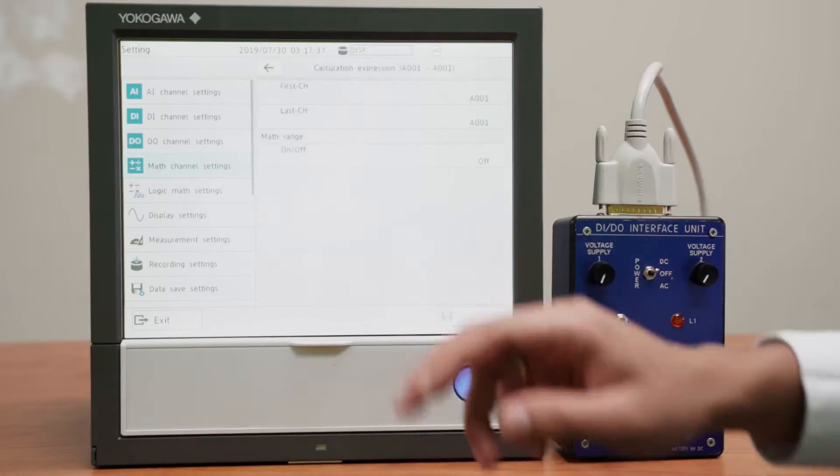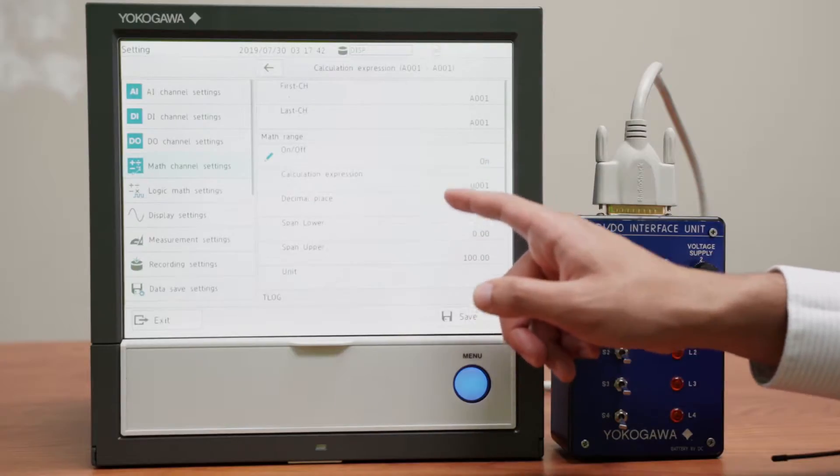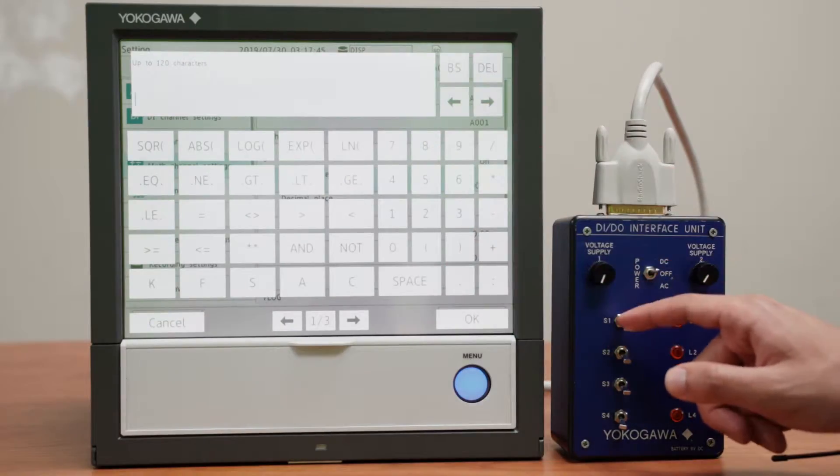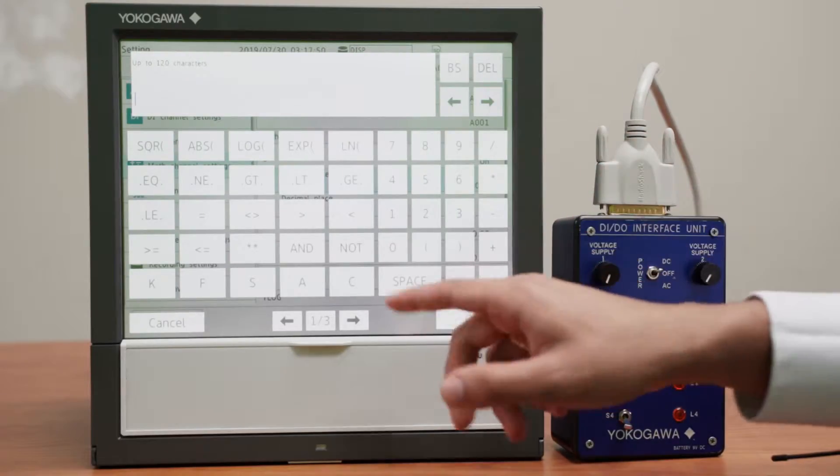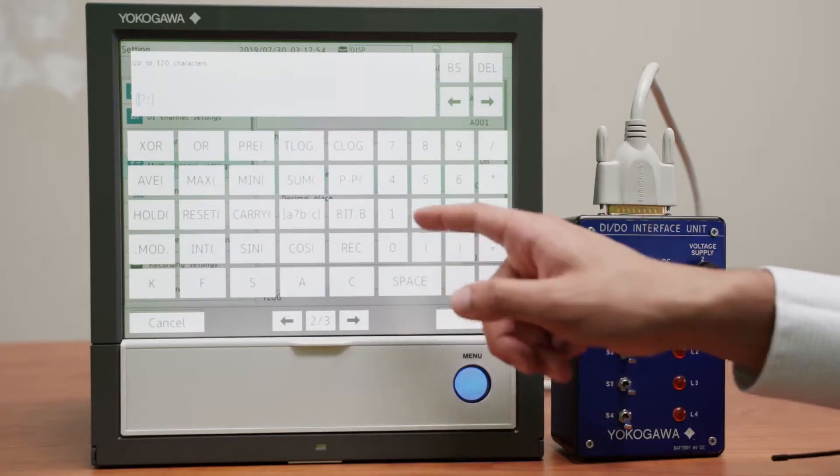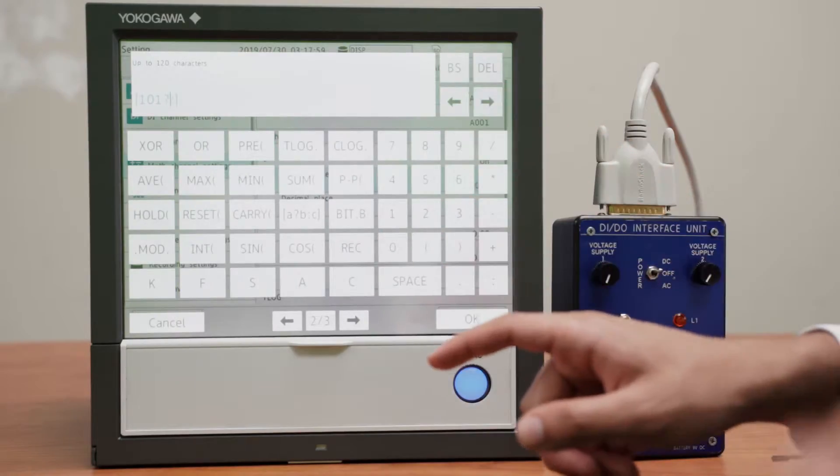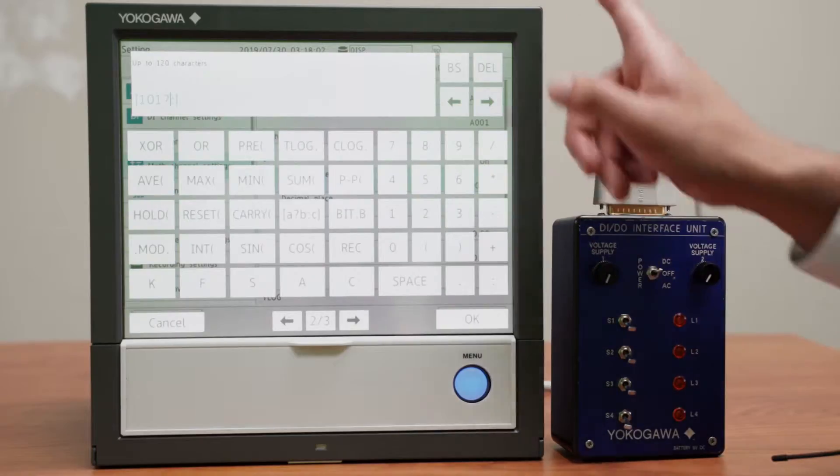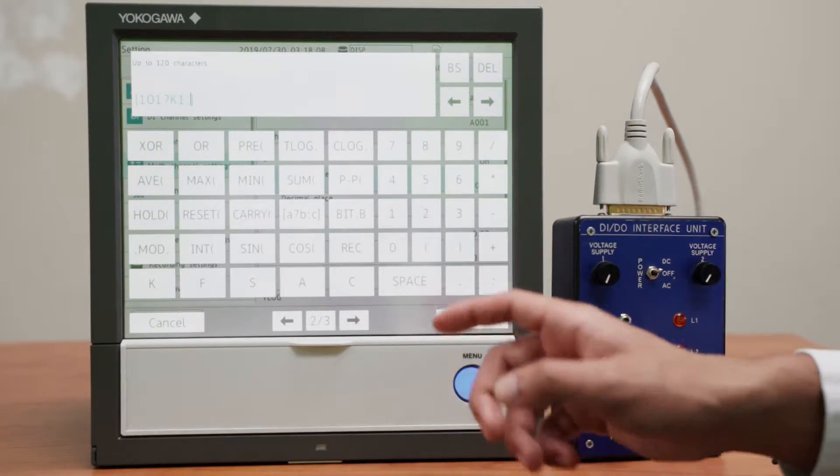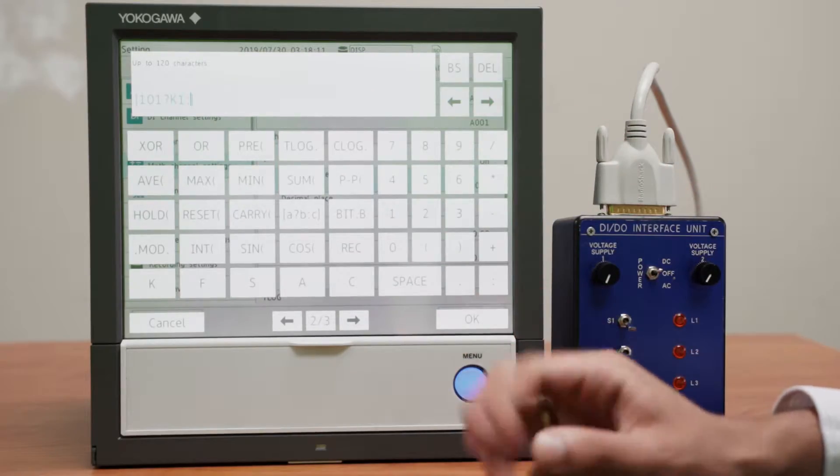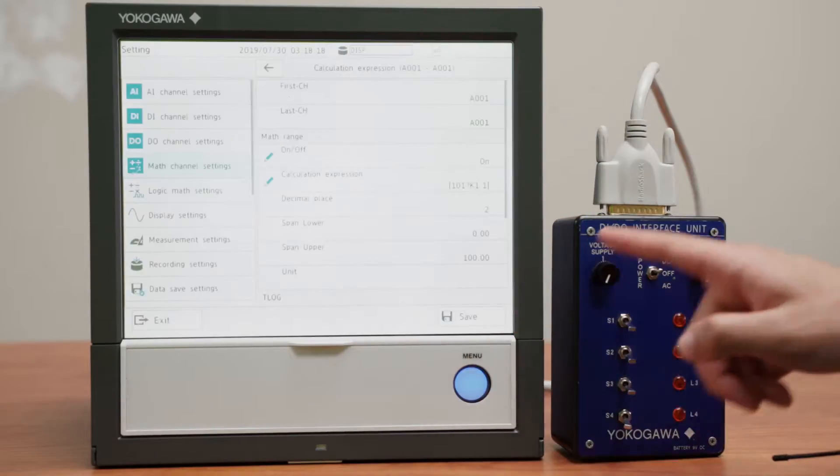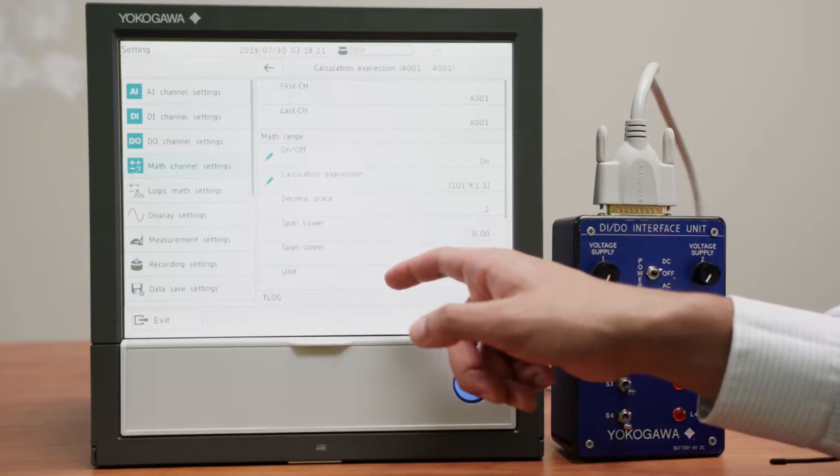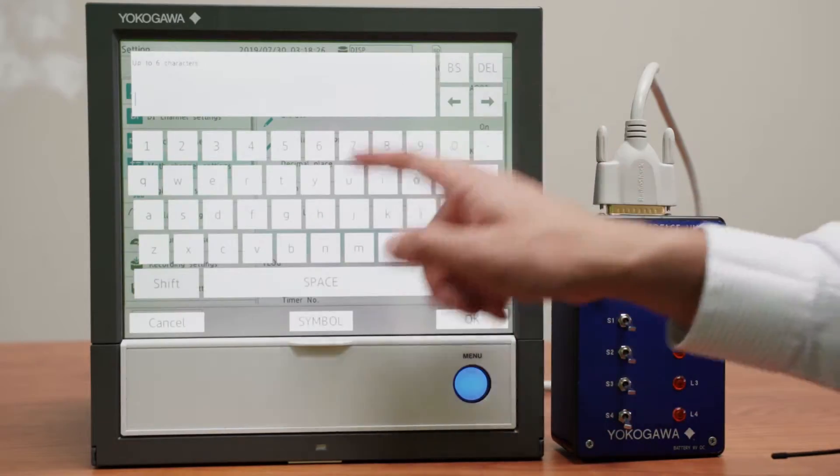And we go to calculation expression and we turn channel A1 on. And the first thing we want to do is make this switch turn off this valve even if it's manually open. And so we need an if then else statement. So if this switch is on, which is channel 101, then the value of this channel, the math channel A1 will be K1, 0. And if it's not on, if this switch is off, it's 0. Then we want that value to be the value of channel 1, which is this input.